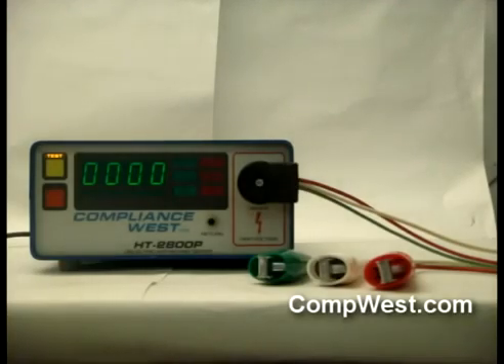The neutral bus and ground bus should not be strapped together at this point. The home must also not be powered otherwise significant damage will occur to the HT-2600P.